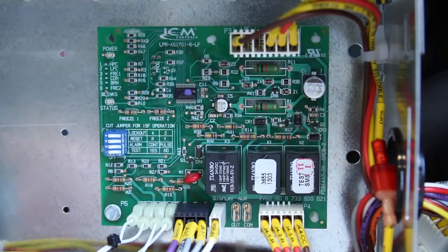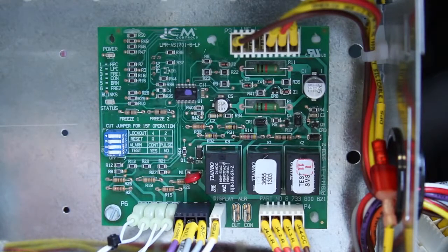Some of the other features of the UPM board include an anti-short cycle timer, which is a 5-minute delay on break timer to prevent compressor short cycling. It also has a random start delay that ranges from 270 to 300 seconds. Also included in the board is a low pressure bypass timer. The compressor will be allowed to continue to operate for 2 minutes after the low pressure switch opens in order to prevent nuisance trips. There is also brownout and surge protection built into the board that monitors low voltage and will prevent the compressor from operating if the voltage drops below 18 volts or rises above 30 volts AC.